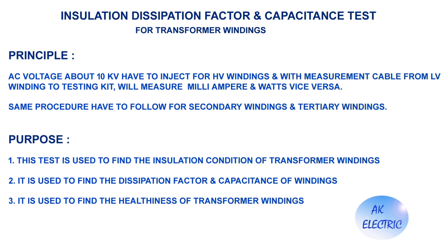Now we'll see the purpose of the test. This test is used to find the insulation condition of transformer windings. It is also used to find the dissipation factor and capacitance of windings, and to find the healthiness of transformer windings.